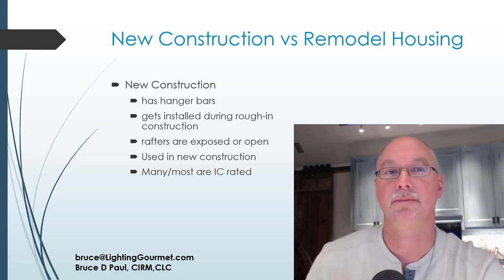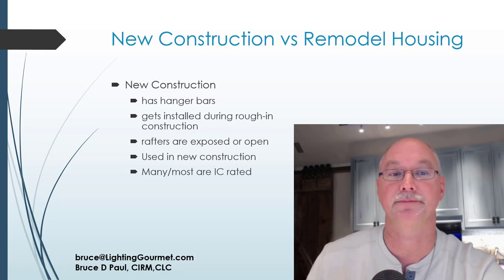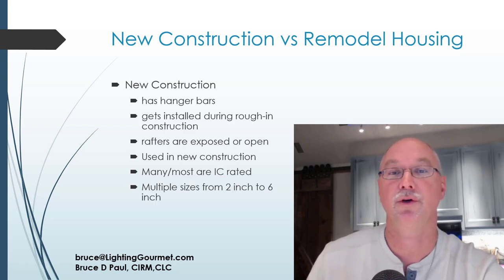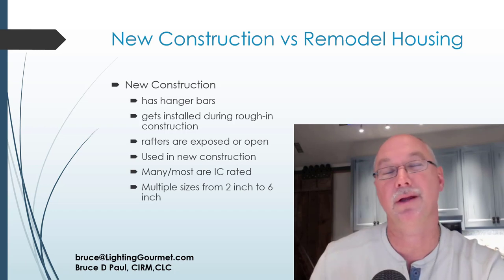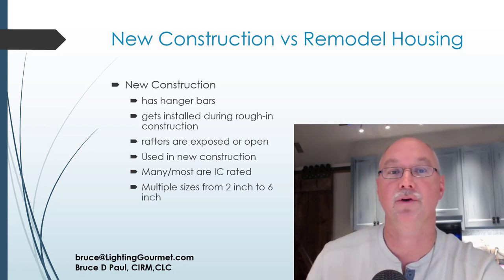Most new construction cans are going to be IC rated, but you need to know whether your can is IC or non-IC rated. If it's an exterior wall, it has to be IC rated — there's another video that covers that in more depth. Sizes vary from 2-inch to 6-inch. While 2-inch isn't very common and 3-inch tends to be a little more expensive, what's most common is 4-inch and 6-inch, and 5-inch cans are not infrequent. So for new construction, hanger bars — that's what you use.